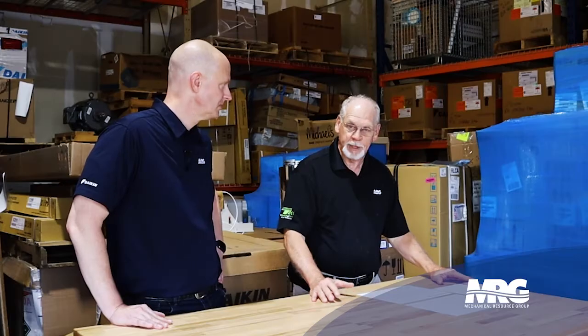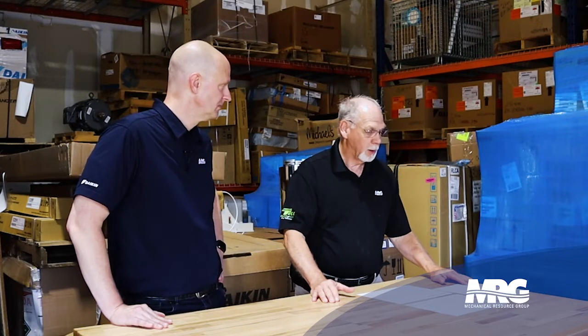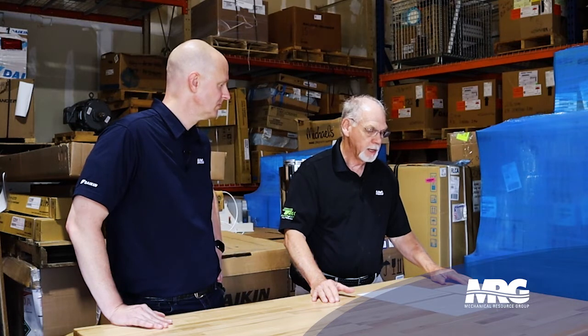And the material that we use is usually B-vent, which is 2 pieces of pipe together, an inner pipe and an outer pipe with an air space in between. And that is so that it doesn't get too hot. So it's double wall B-vent. And that's usually what we use with the old style open combustion atmospheric type boilers. That's what we used to do when I started. That's about the only thing that was there.